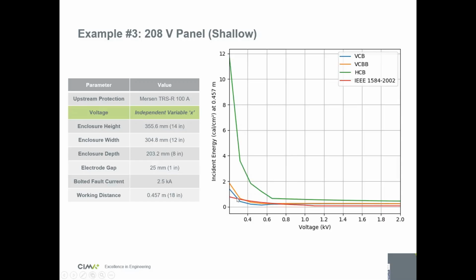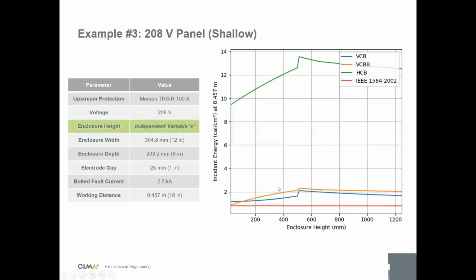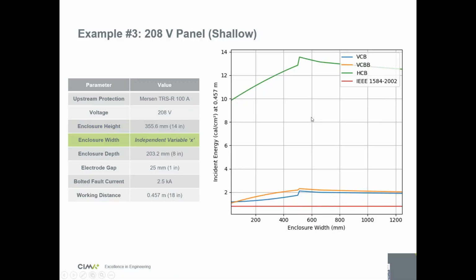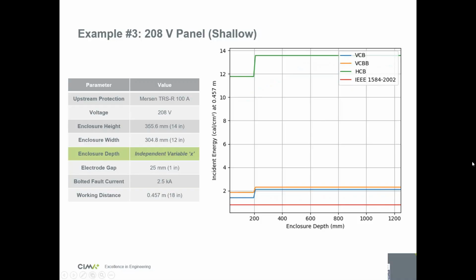And then there's some overlap here between the VCB, VCBB, and the last standard. So it hasn't changed much unless it's HCB. If it's HCB, it has changed a lot. HCB again is very, very much higher when you have a shallow 208 volt panel. In this case, your enclosure height will have a big impact if you're HCB, but if you're VCBB and VCB, it's much lower. The width is about the same as the height. And then your depth, this is where your depth has an impact. If your box is shallow, so if your enclosure depth is below 200 millimeters, which is 8 inches, your energy will be lower. Then if it's higher, it becomes typical and your energy increases a little bit.